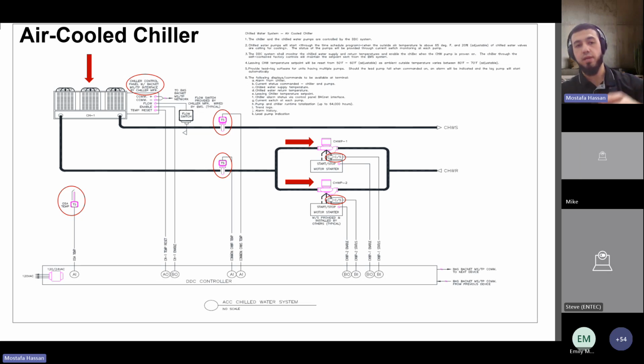There it is. Now, Emily showed this schematic yesterday without the sequence of operations. Today we're going to build it together, and we're going to look at the components, the field devices that make this up, and line by line how the system actually operates in the field. So the chiller and the chilled water pumps are controlled by the DDC system. There's your chiller. If you didn't see it yesterday in 103, it's an air-cooled chiller, and there's a note that it comes with a BACnet MSTP interface by the chiller manufacturer.